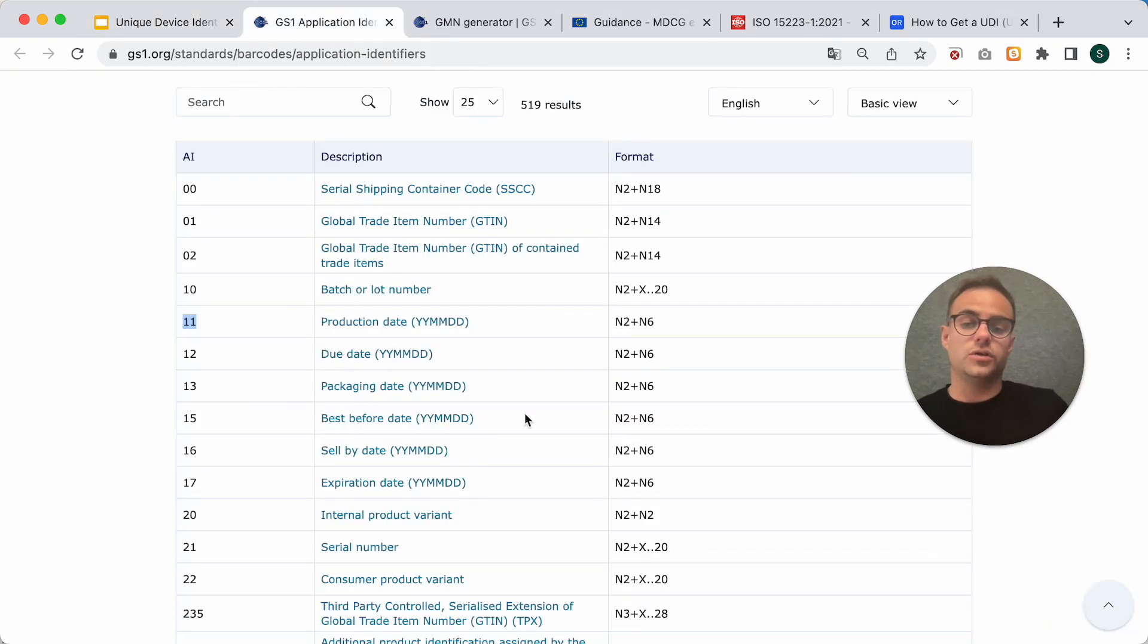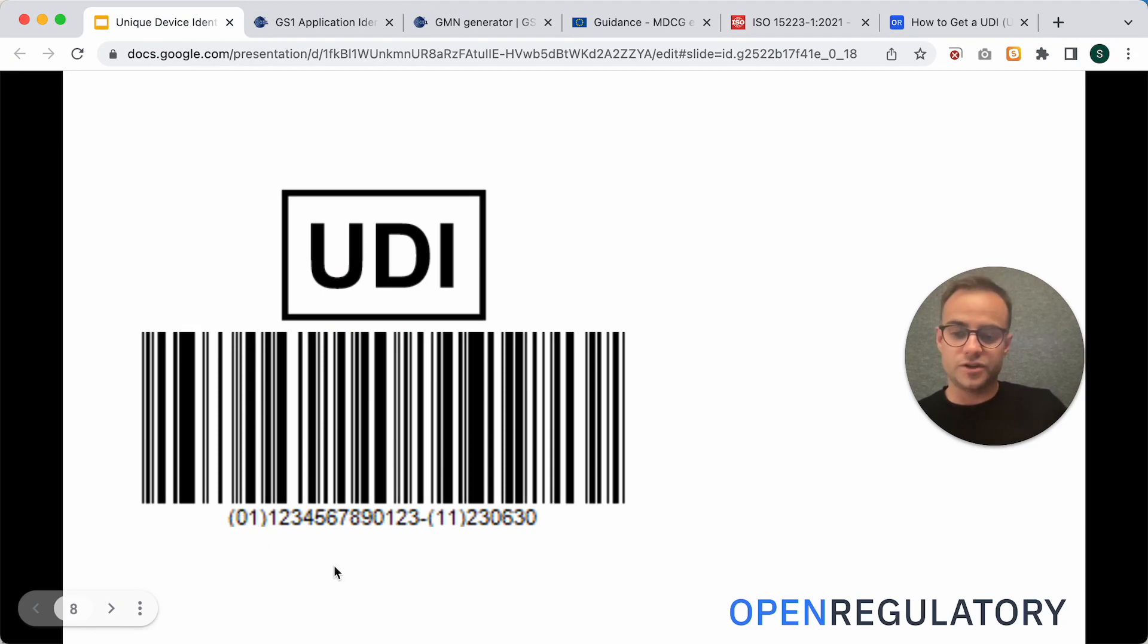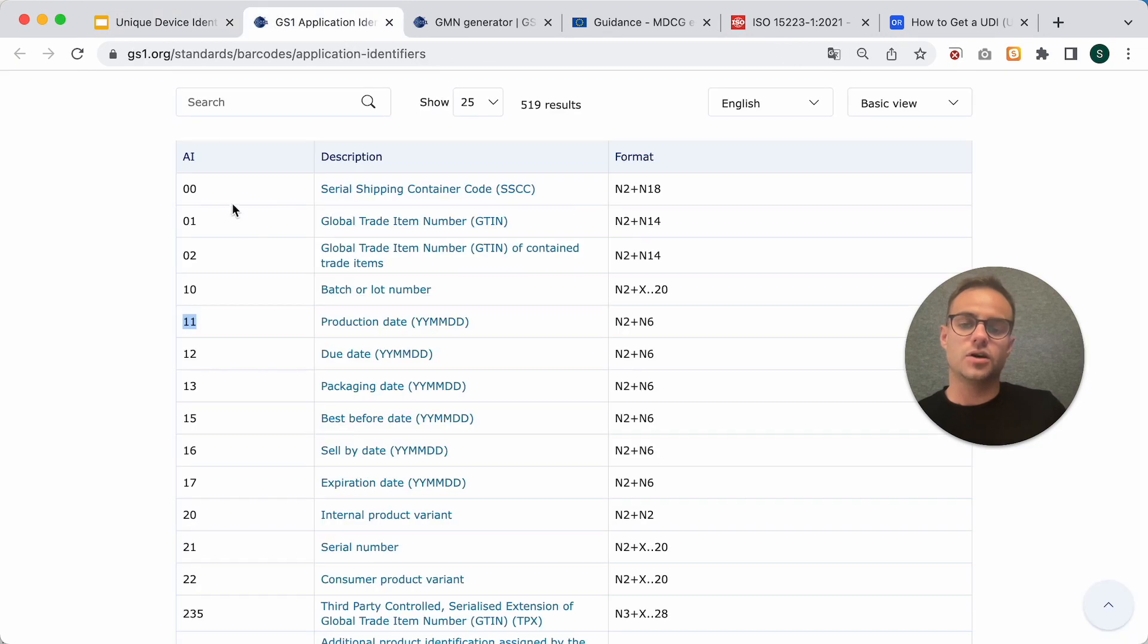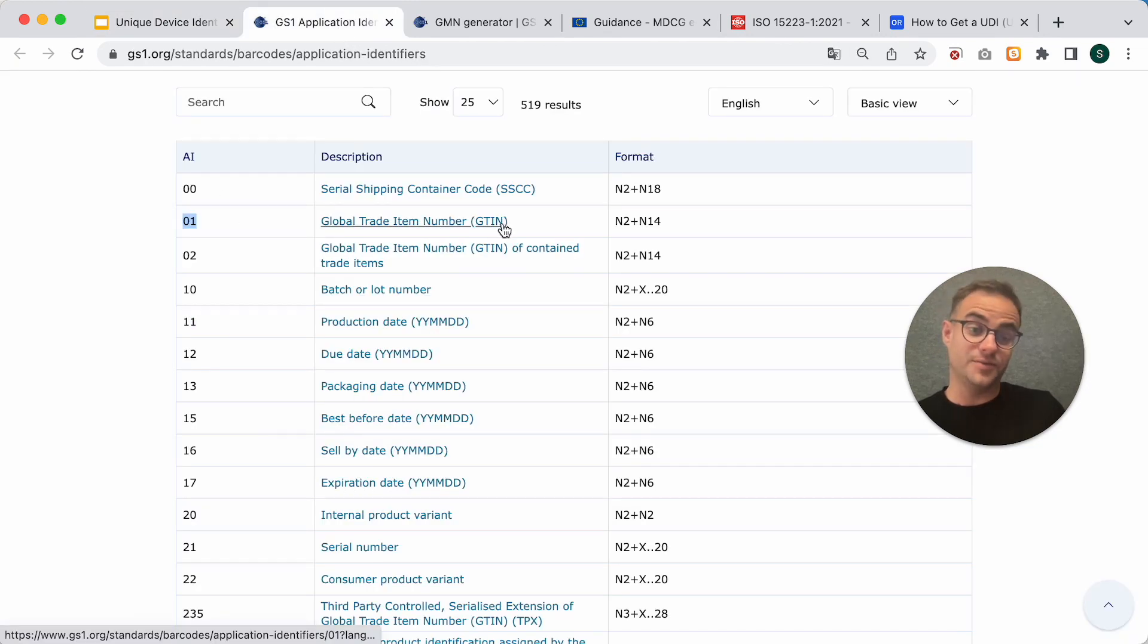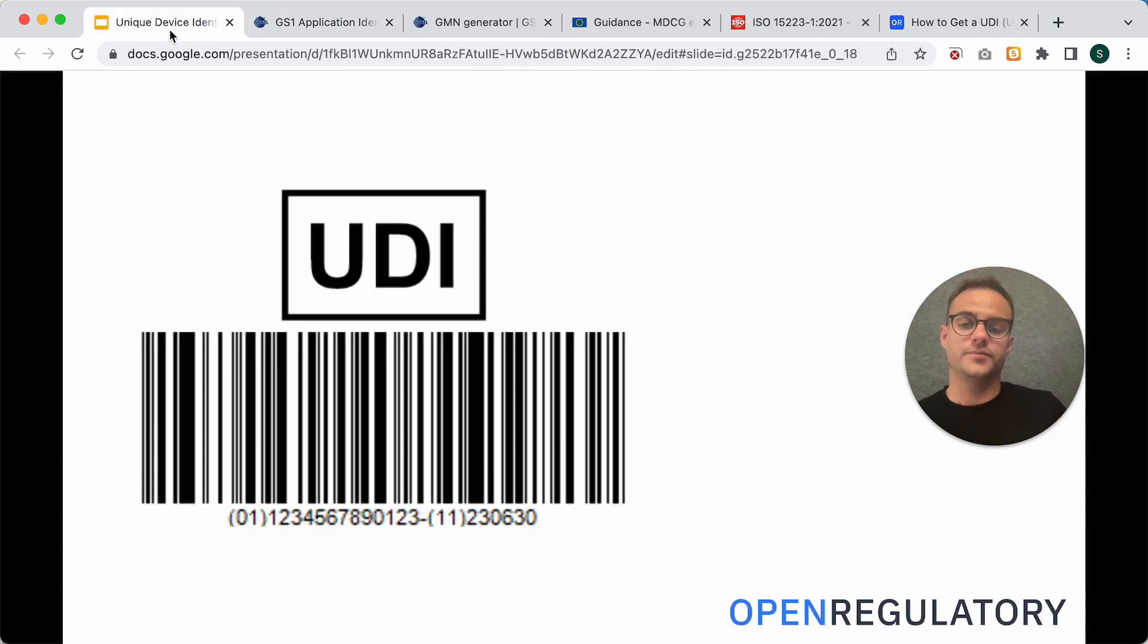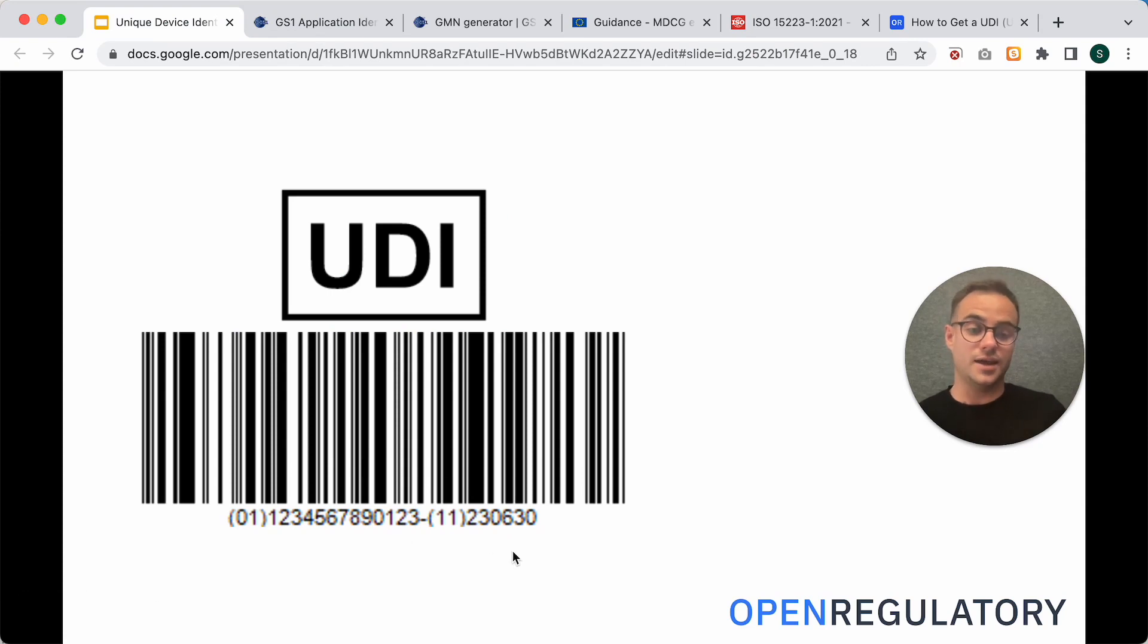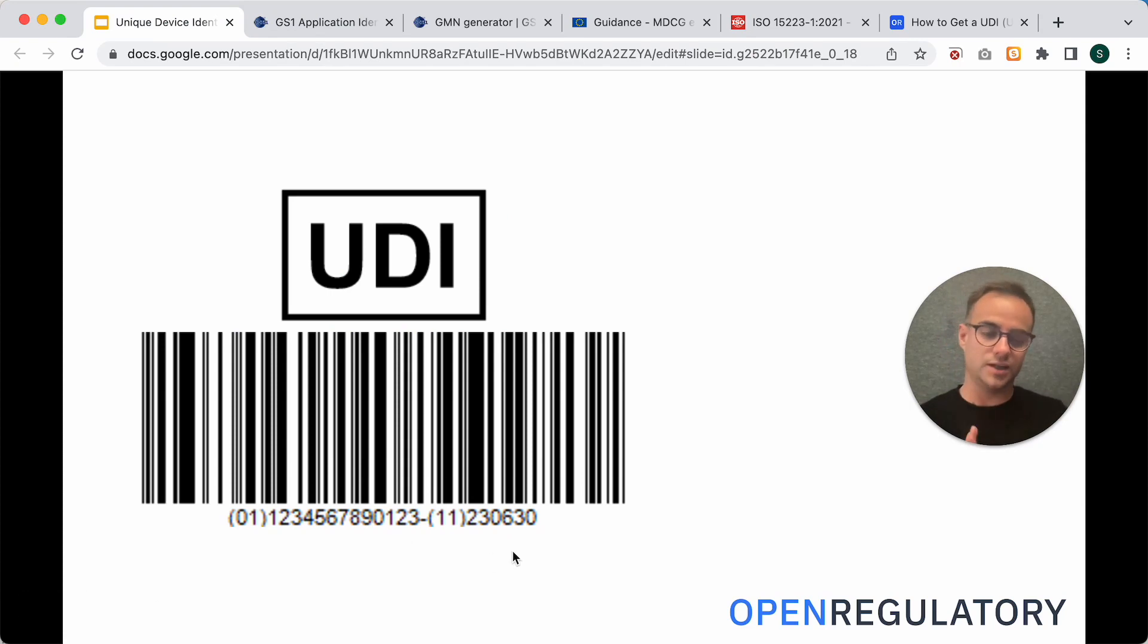And when you look at this list, it helps you also understand what this first number is. So, if you have a 01, that encodes for GTIN. So, that's our UDI-DI. So, in fact, here we have the UDI-DI and the UDI-PI. And that's a complete UDI. That's how you would find it on the product.